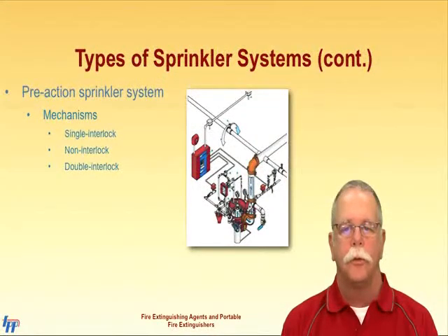A pre-action system is used when it is important to minimize water damage. They may be found in computer rooms, document storage areas, or in freezers. These systems have closed heads, a fire detection device, and a deluge-type valve. The piping is dry, and water is not introduced until a signal is sent from a detection device.